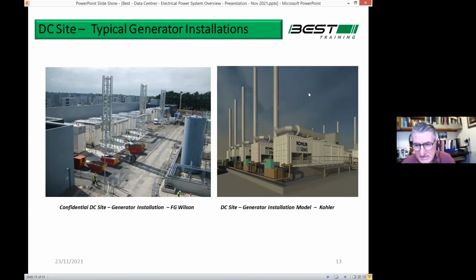This one I think is a CGI, but you get the drift. It's showing the generators, the flue system going up here, and then you see this big space down here. That's actually the belly tank. So that's the container, the generator in the container, and all of this space below is fuel storage to give you typically 48-hour storage. And the green box here is your fill cabinet where the fuel comes in.